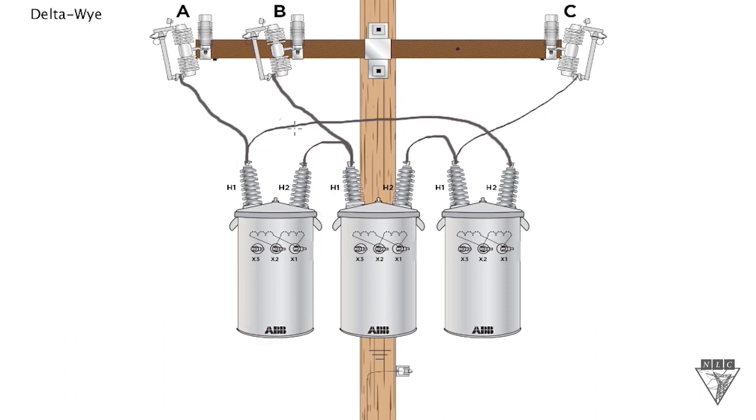If you look at the center one, let's do another example. The H1 on the center transformer goes up to B phase, and the H2 on the center transformer comes over here and it goes up to C phase. So there's another phase-to-phase connection between B phase and C phase. All right, so that's our primary connection on the delta, delta Y bank.